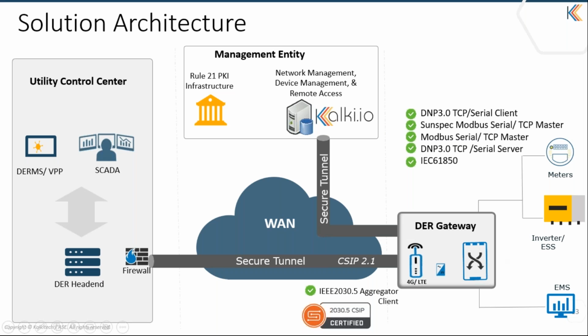So the gateway's connection to the field assets like EMS systems, inverters, or meters can be over different communication media like DNP3 TCP or serial, SunSpec Modbus TCP or serial, standard Modbus, could be IEEE 2030.5 as well. And that will be the downstream from the gateway to the field devices, and for the northbound, the connection with the utility system will be over the 2030.5 aggregator client. Data will be pushed to the head end system, and from there it will be sent out to other applications like DERMS or VPP or SCADA systems, which are available in the utility premises.